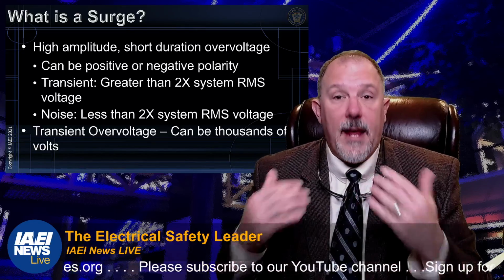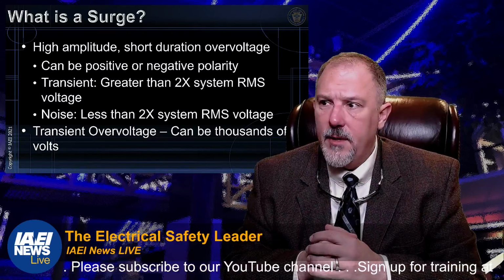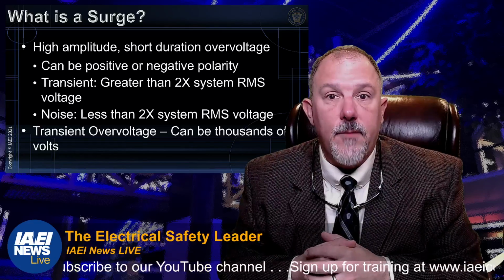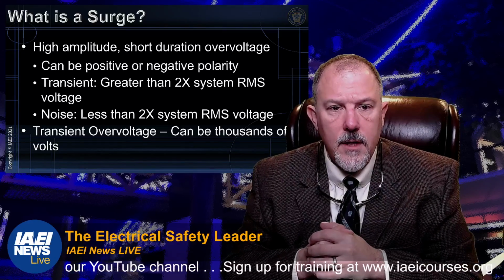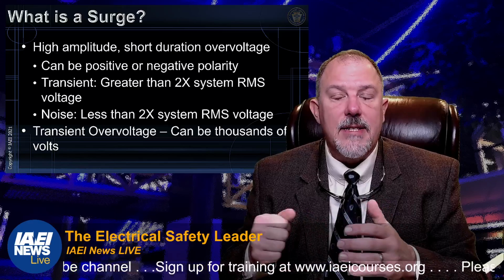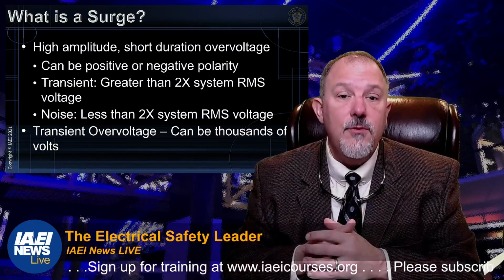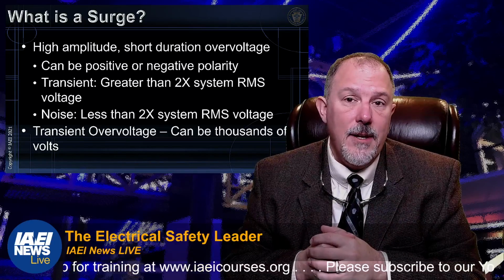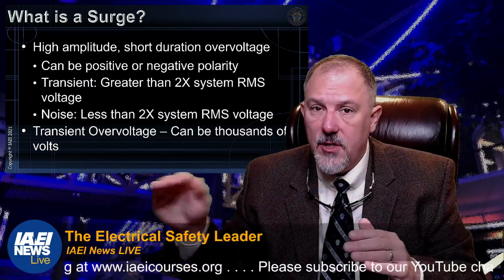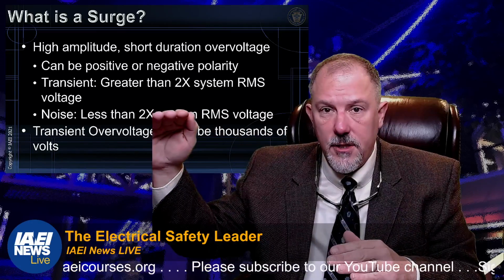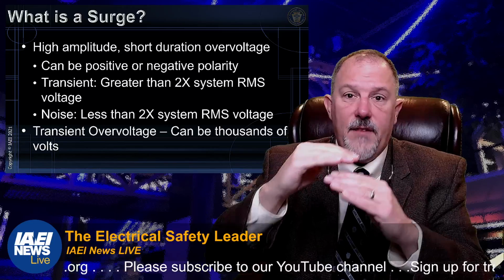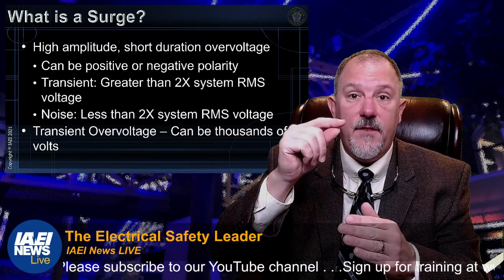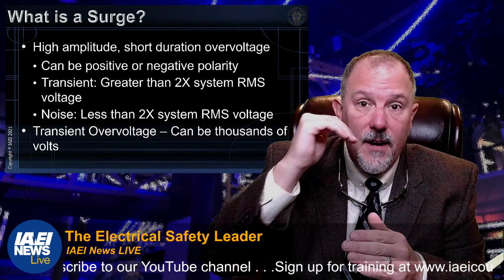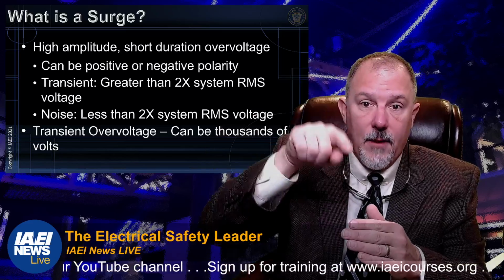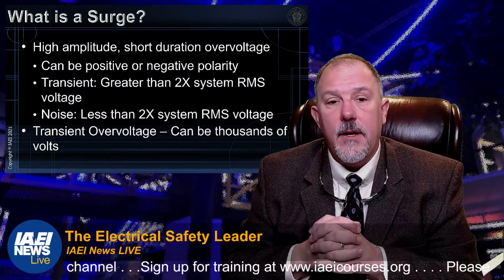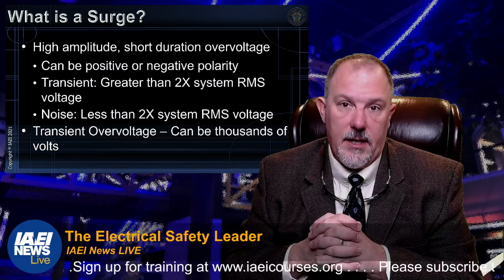Now, from an amplitude perspective, I believe we have some sine waves to show you. But these transient events can be up to greater than 2 times the system RMS voltage. Now, if you think about RMS as a root mean square, then remember you have a peak voltage, and the worst case would be a transient event at the peak of your sine wave, right? That would go up and over in a transient event. That would be your worst case scenario.